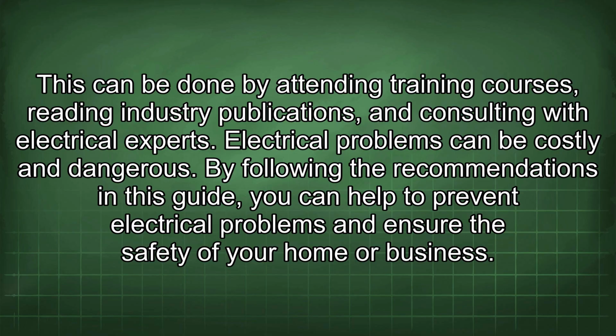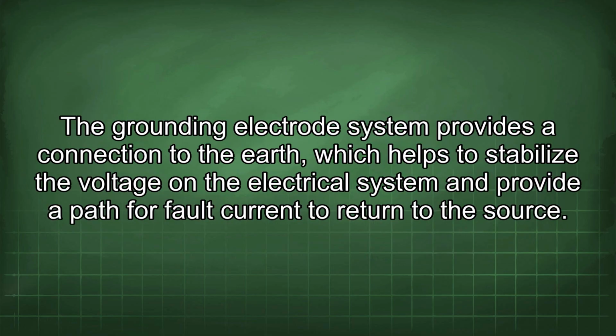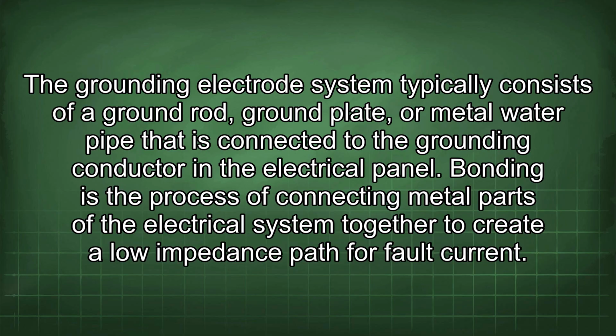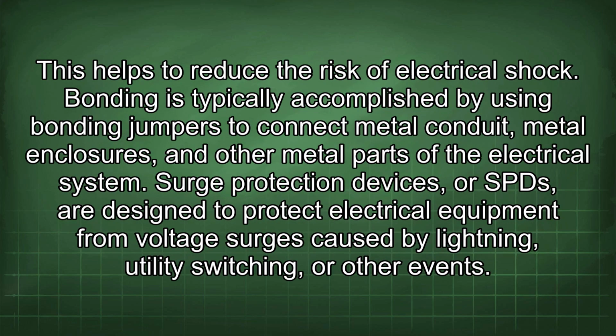The grounding electrode system provides a connection to the earth, which helps to stabilize the voltage on the electrical system and provide a path for fault current to return to the source. The grounding electrode system typically consists of a ground rod, ground plate, or metal water pipe that is connected to the grounding conductor in the electrical panel. Bonding is the process of connecting metal parts of the electrical system together to create a low impedance path for fault current. This helps to reduce the risk of electrical shock.